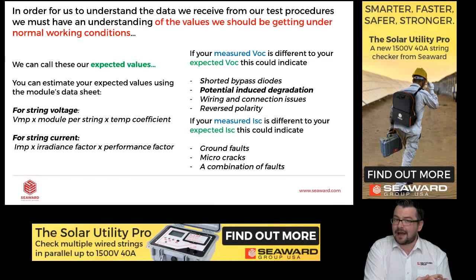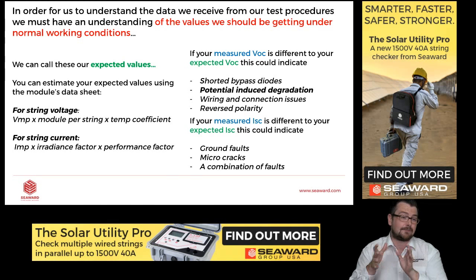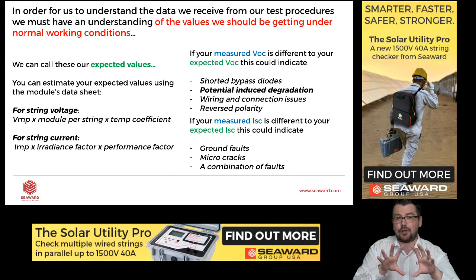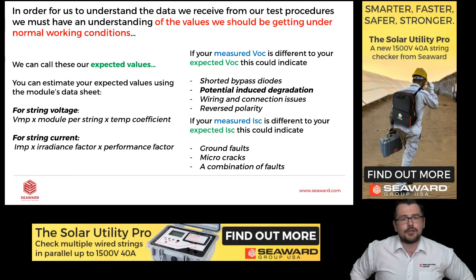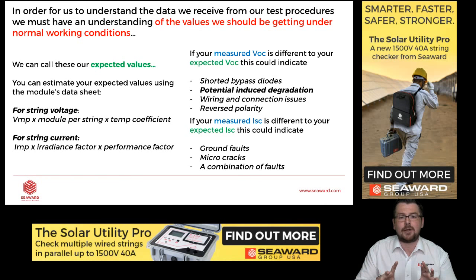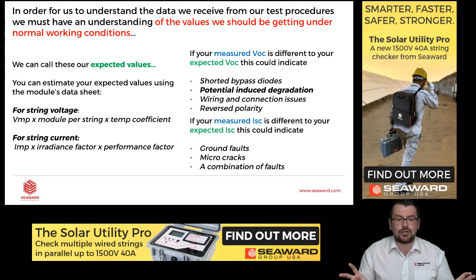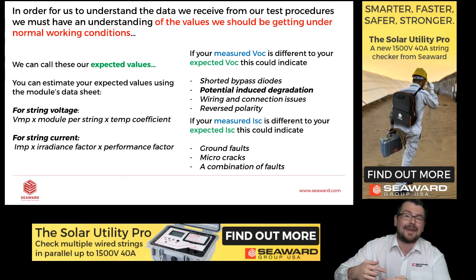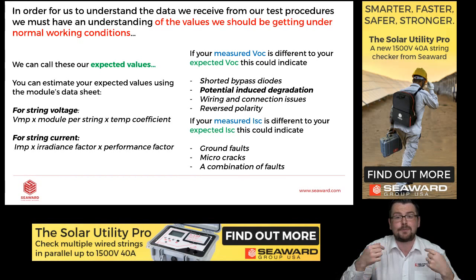Now, if your measured values are not in line with your expected values, this could indicate a few different problems for us. So if the measured VOC is not in line with your expected VOC, this could mean that we have shorted bypass diodes, PID, wiring and connection issues, and that's the main problem. And particularly if you're commissioning a system and not maintaining a legacy system, reverse polarity. So maybe it's a Friday afternoon, the guys, they were trying to get away quickly, they put a positive on a negative, that's reverse polarity. That's causing us a real problem.